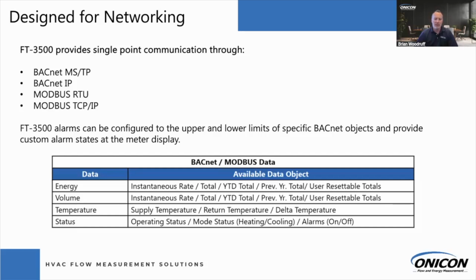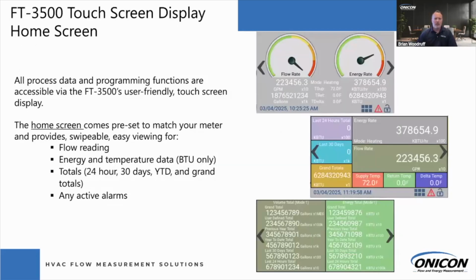You can also set up some of those object points to do some of your alarms at the upper and lower limits. At the bottom there, you're going to see some of the data and available object points that you have available. What's great about this is you won't need any GUI software or laptop to do any changes. It's all field configurable. So for example, you're able to change the IP address, the subnet mask and gateway, all through the actual remote transmitter that accompanies the meter. The touchscreen display. So we're really excited about this.